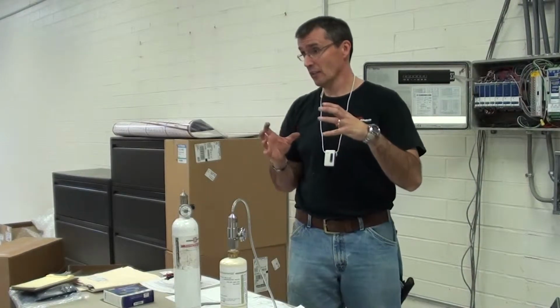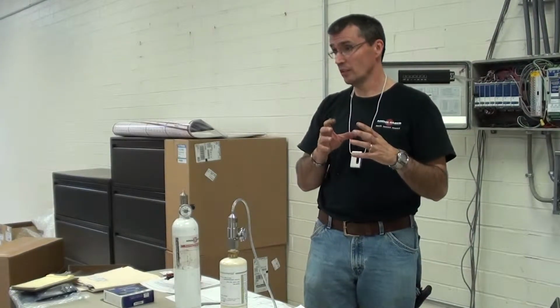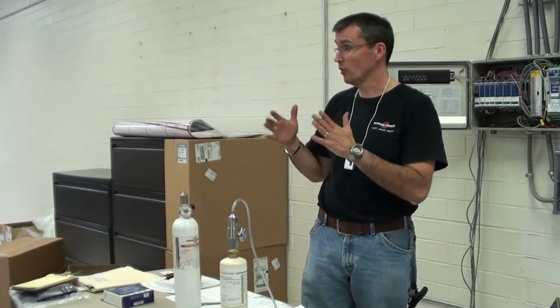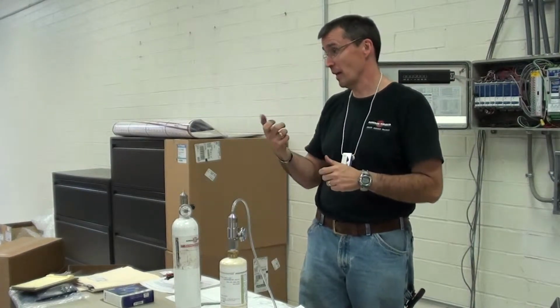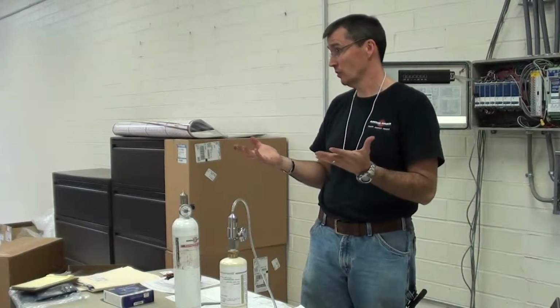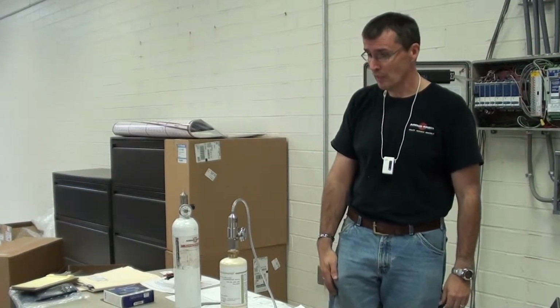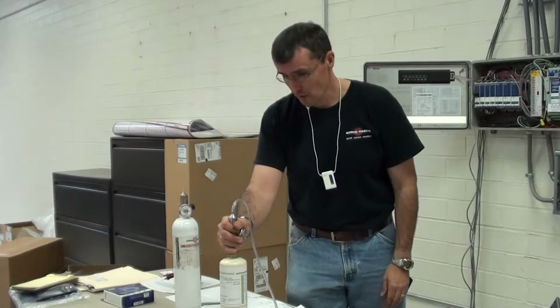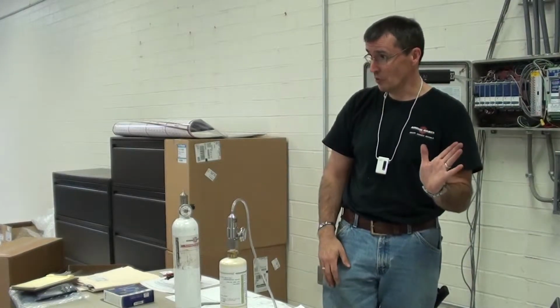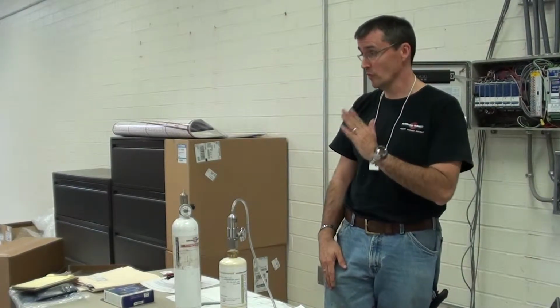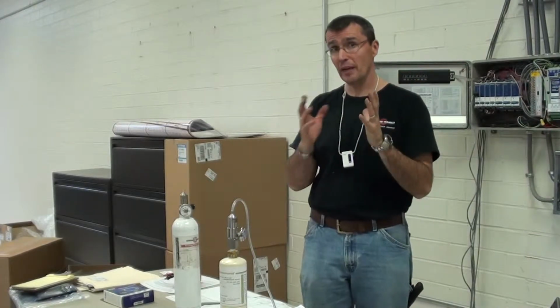So you can't actually have an ignitable environment until you reach 100% of the lower explosive limit. You can strike a match all day at 99% and it won't explode. But at 100% you can actually have ignition. Okay? Alright, so again we're going to use 50%, but we're going to set our display to read 35%, use that correction factor of times 0.7. So that's going to be our span gas.